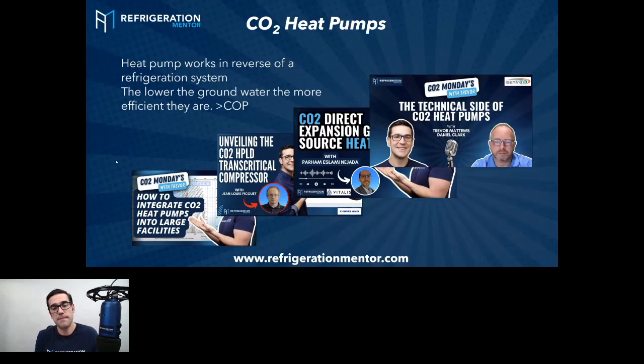We're taking that condenser where we're usually rejecting heat in refrigeration - like when you're rejecting heat outside in refrigeration or air conditioning. Instead, we're rejecting that heat into the space, the house, the building. Even though the air is really cold - and it took me a long time to realize this - there's still usable heat in that cold air that we can transfer indoors.